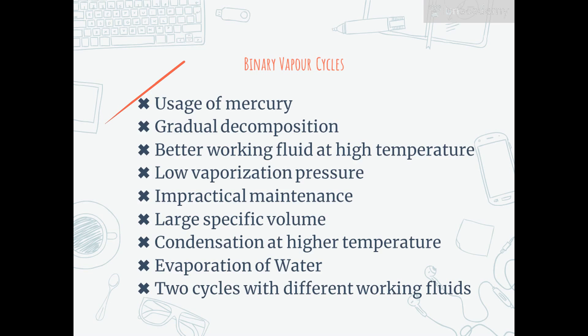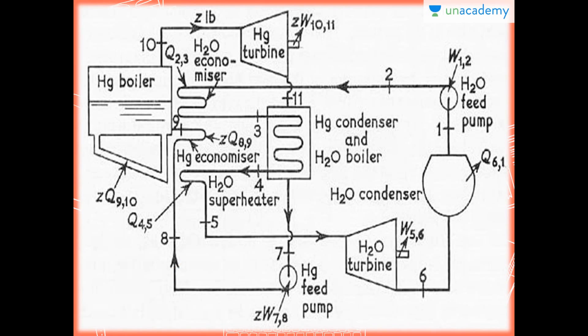Its specific volume at such a low pressure is very large and it will be difficult to accommodate such a large volume flow. Thus, for these reasons, to take advantage of the beneficial features of mercury in the high temperature range and to get rid of its deleterious effects, we use mercury at the high temperature range and the mercury vapor leaving the mercury turbine is condensed at a high temperature and high pressure. In the binary or two-fluid cycles, two cycles working with two different working fluids are coupled in series and the heat rejected by one is being utilized by the other. You can see here the flow diagram of the mercury-steam binary cycle, showing the Hg turbine, the Hg boiler, the superheater, and the economizer.